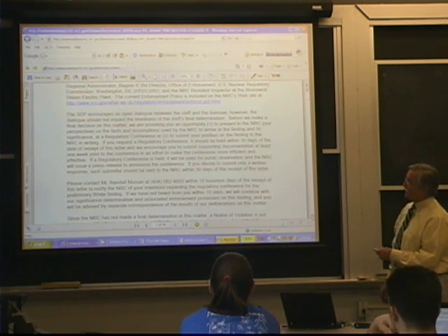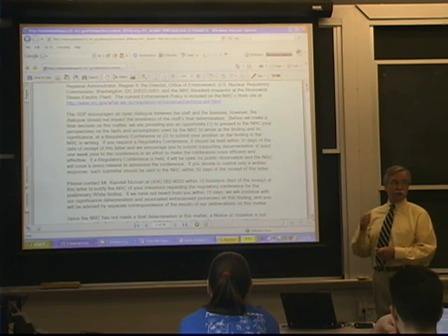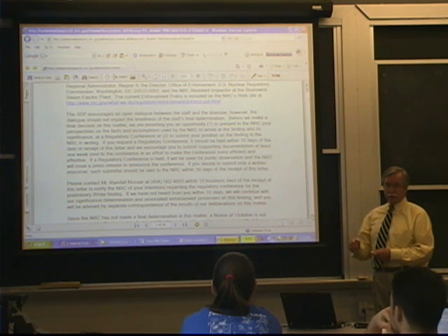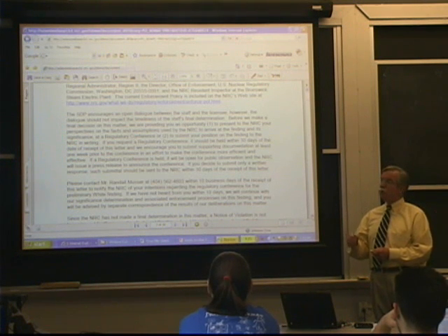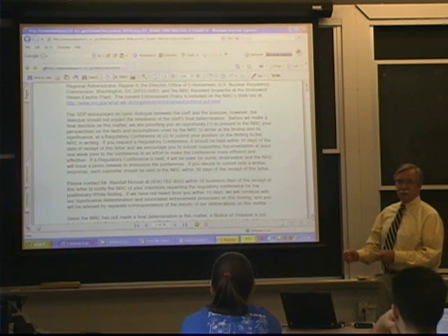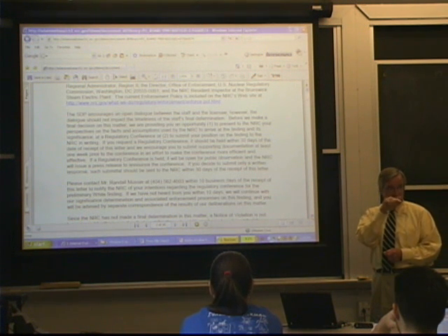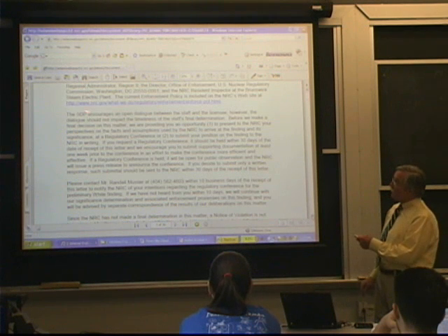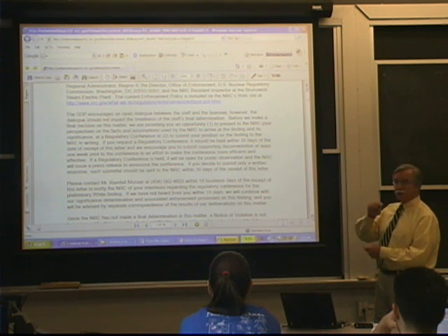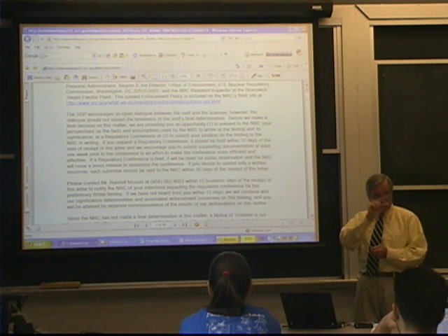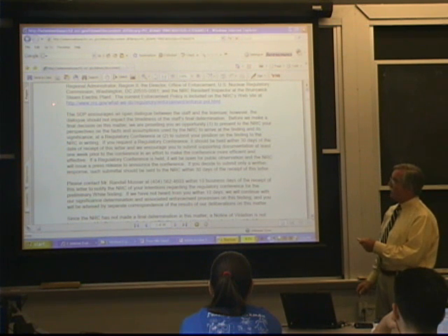Now this SDP is the significance determination process. That is the use of risk to determine whether you are in the white zone or the green zone. Remember we talked about these little delta CDF curves? When you do the analysis, if that risk number changes by that arbitrary change, in terms of 10 to the minus 5, 10 to the minus 6, you will go into the white.